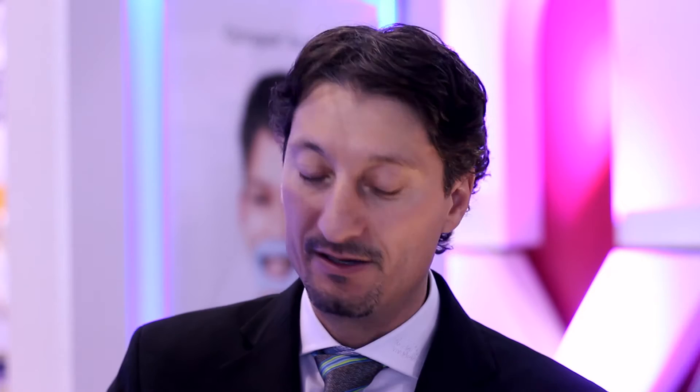It looks like the spot where I put my light on looks a little larger than what I'm usually used to seeing. Right. Most radiometers measure light intensity using a small light sensor — like a little circle. Whereas the Bluephase Meter 2, the whole entire surface area is one large photosensor. So it will capture all the light being emitted and provide much higher accuracy.